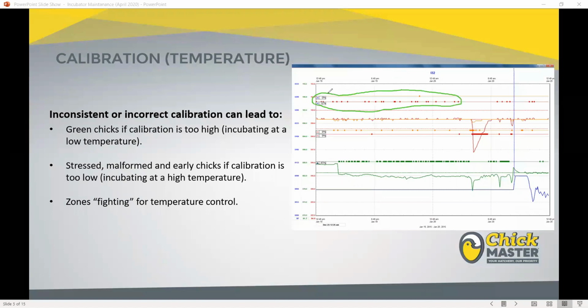So over on the left-hand side of the Maestro, we can see that zone 1's been cooling for 12% of the time and zone 2's been cooling for 0%. These two zones are in effect fighting each other for the condition inside the cabinet. To me, that tells me that one of those zones is calibrated either too high or the other zone is calibrated too low.